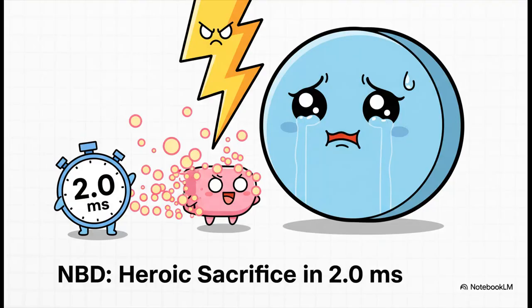So what was the result? Well, during this massive fault, that energy limit was blown past in just 0.002 of a second. The safety valve fails, the entire NBD is bypassed, and all that crazy fault current flows harmlessly to ground. And here's the crucial point: this isn't a design flaw. This is the design. The NBD is literally built to sacrifice itself to save the multi-million-dollar transformer it's there to protect.